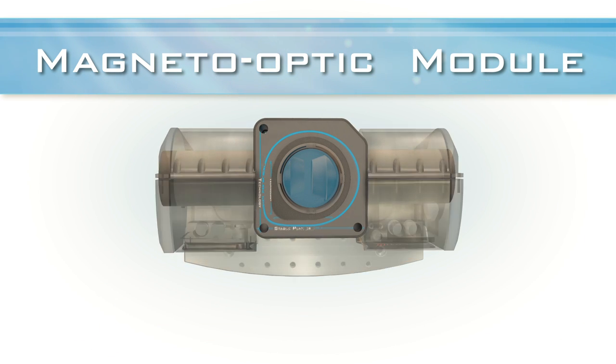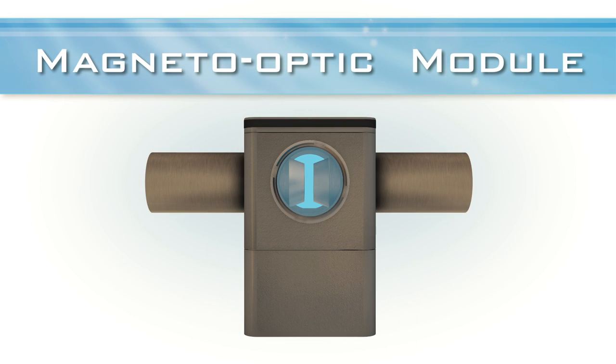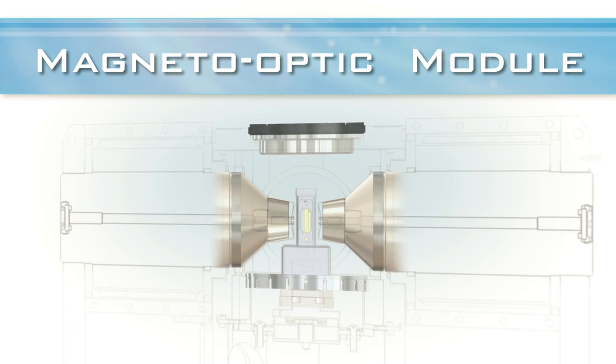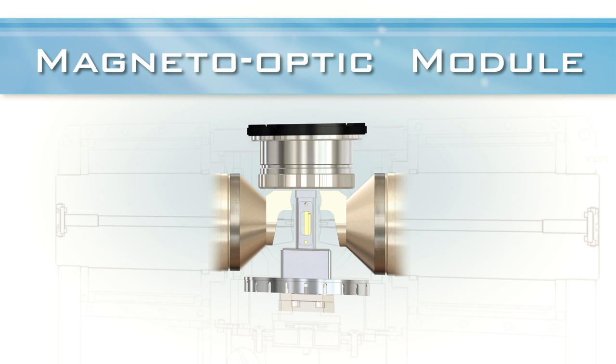Optical access is provided from above and both lateral directions, including the magnet bore with optional lens-integrated pole tips for focusing. Montana Instruments also offers options for higher magnetic field with closer pole tips, and a recessed objective which allows for closer working distances between the sample and the objective.